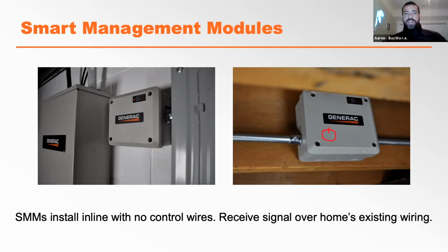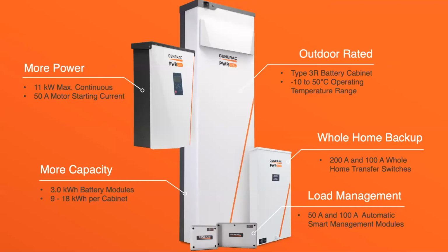We had another question from someone with a client interested in storage primarily for a sump pump, but who only has room on the roof for a 6.4 kW system. Does Generac have any smaller systems available? No, the 7.6 inverter is what we have right now, but you don't have to install the full capacity into it. That's fine if you only want to install 6.4 kW of solar into that inverter. You just want to make sure you're sizing your battery, meaning installing enough battery modules to accommodate that load. You don't have to max out on the PV DC side; you can install a system that's right for your customer. It's a very flexible situation when you're working with Generac.